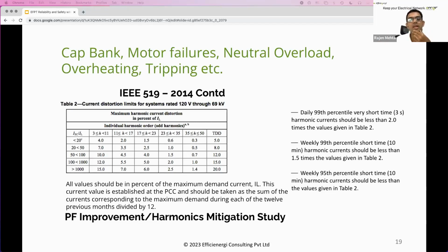Are these IEEE 519 limits at the grid level? And what are the limits at the individual PMC level? So strictly as per IEEE 519, these limits apply only and only to the PCC. They do not apply, nor does IEEE recommend that they be applied, to an individual PMC. It is the choice of the individual consumer or the measurement person to apply them at a particular point of measurement inside the facility. But remember, that is your choice.